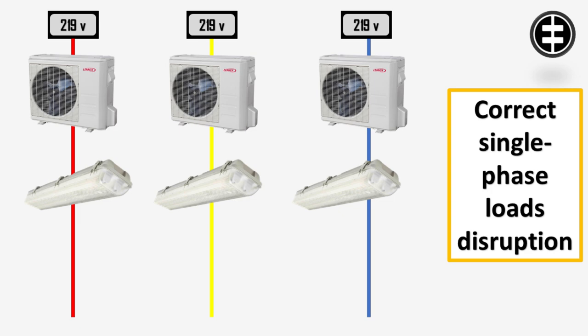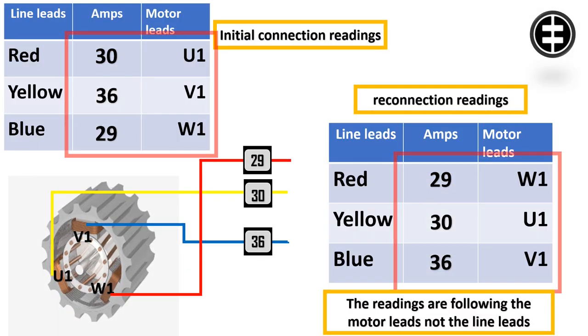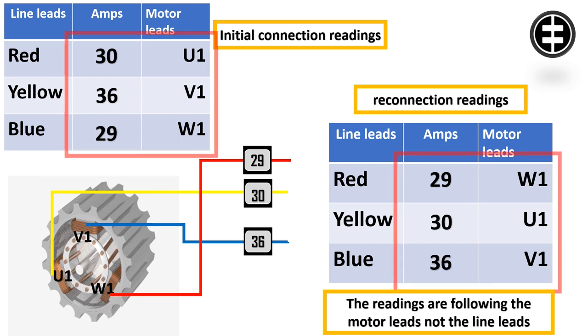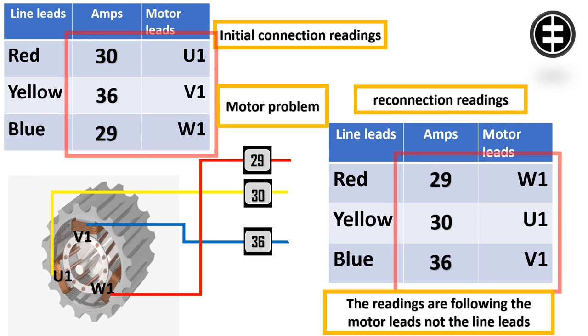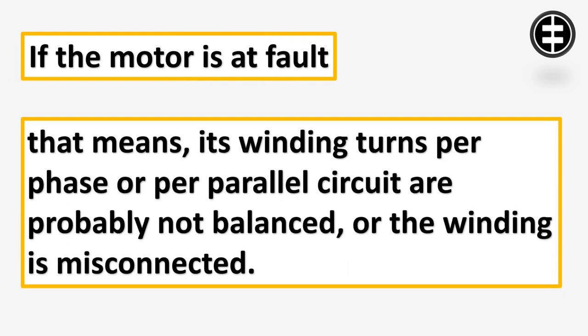If the high and low readings follow the motor leads, then the motor is the source of the problem. If the motor is at fault, that means its winding turns per phase or per parallel circuit are probably not balanced, or the winding is misconnected.